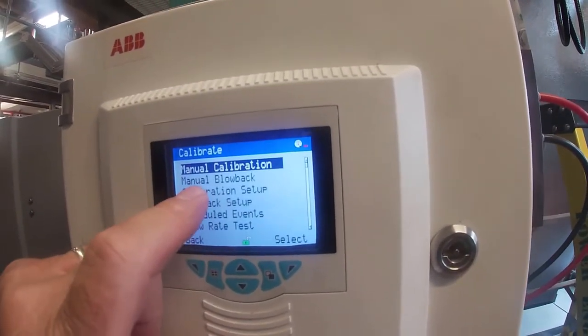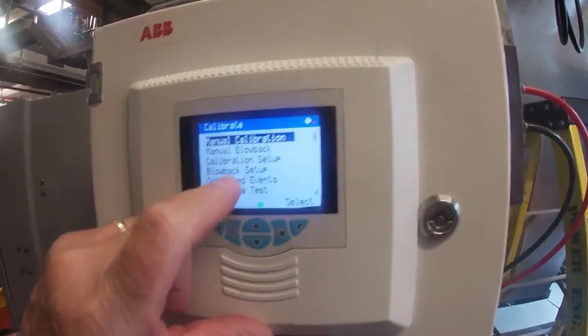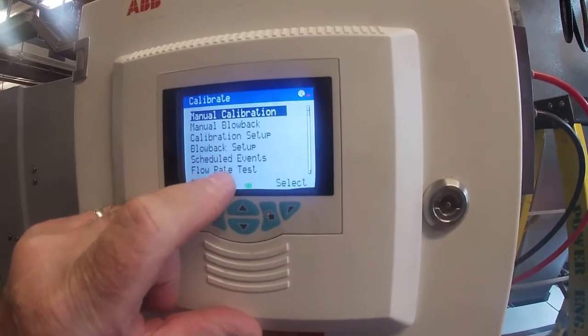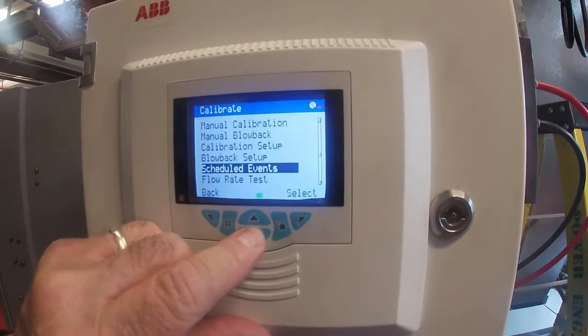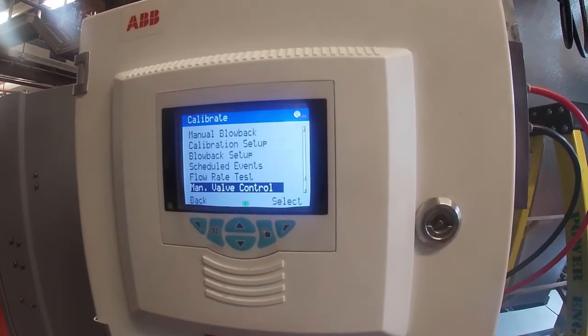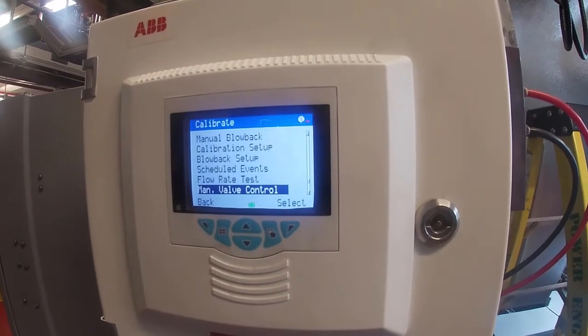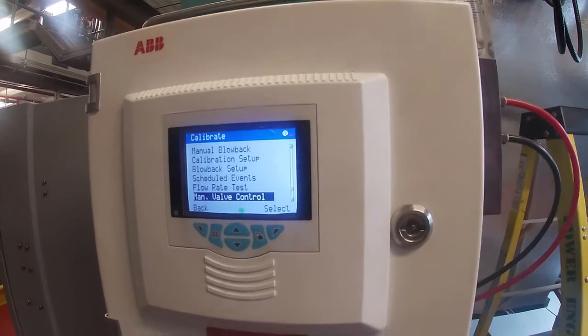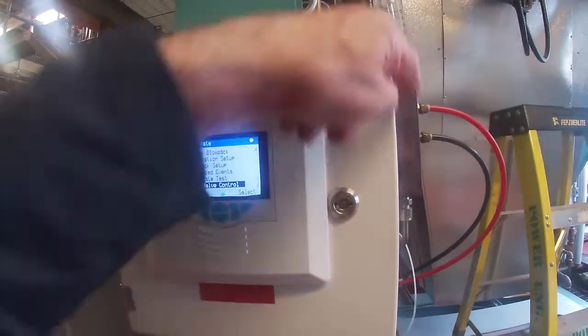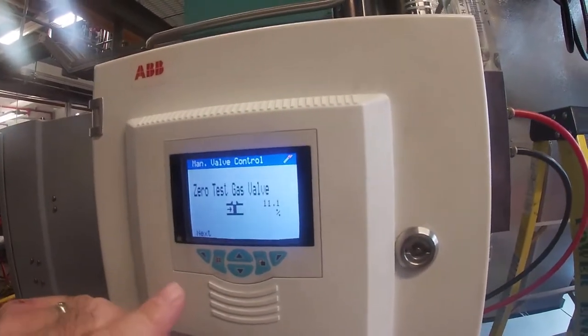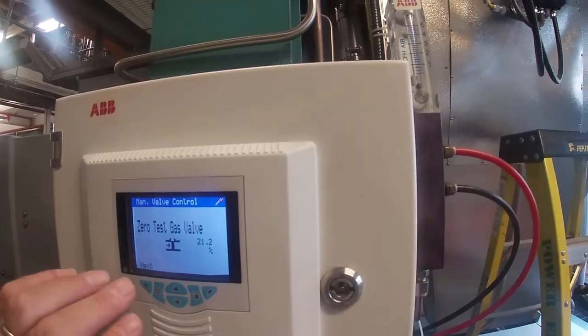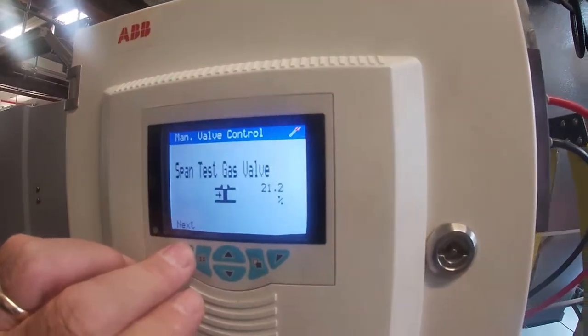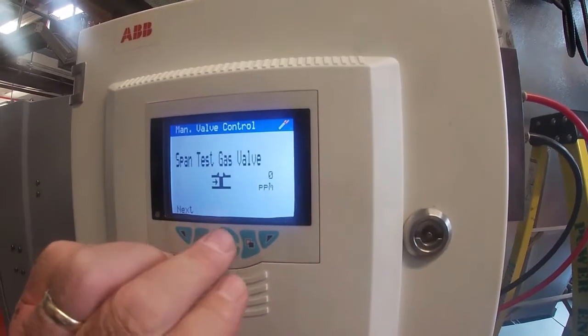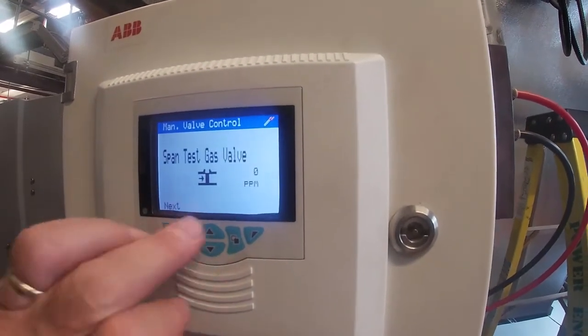I want to go now to actually put that set up, so go down. I think I've got to go back down to here. Yes, manual valve control. I'm going to actually inject some span gas first and then the 0 gas. The reason for that is that I've already got span gas in these lines all the way through here, so I might as well do that first. So I'm going to select it, and 0 test gas. I'm going to go next, span test gas valve. That's the one I want. I'm going to open that up.